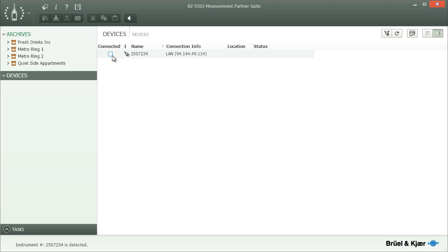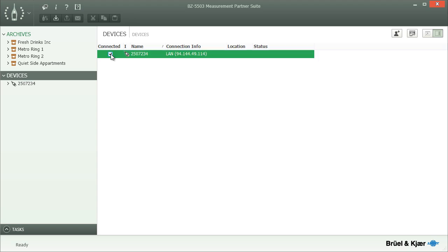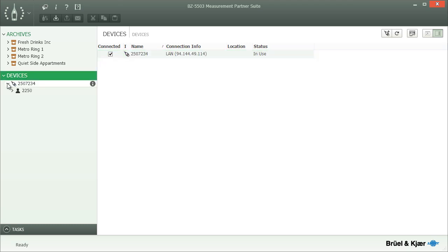However, the instrument will not automatically appear in the tree. To avoid unnecessary remote communication, you should only select the instrument's checkbox when you need to interact with the device. It will then appear in the tree and be available for browsing and data download.